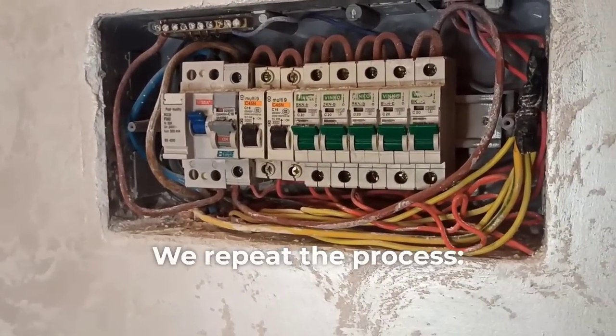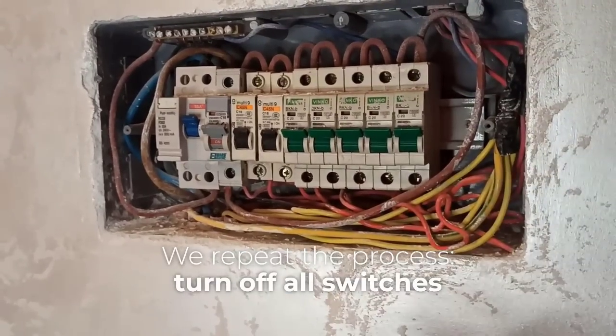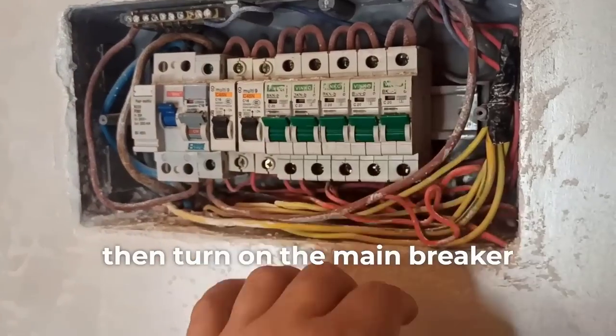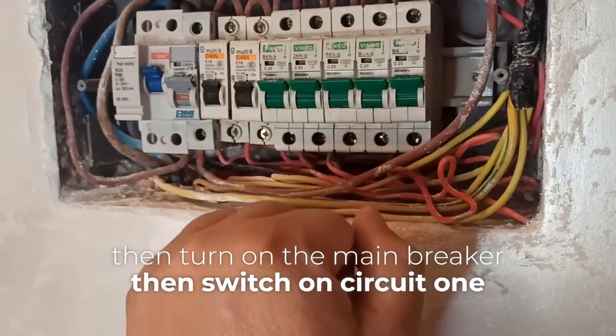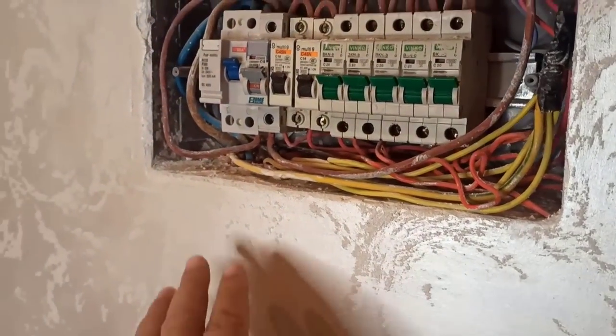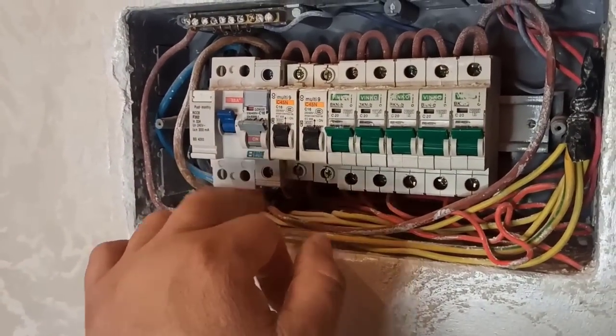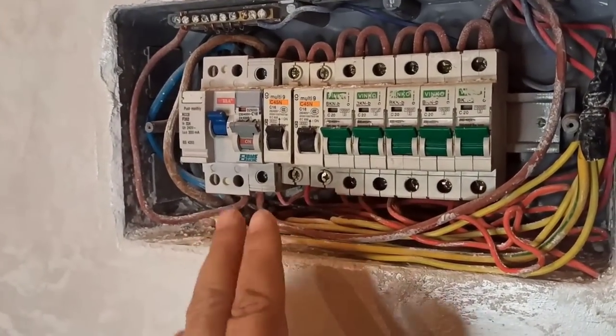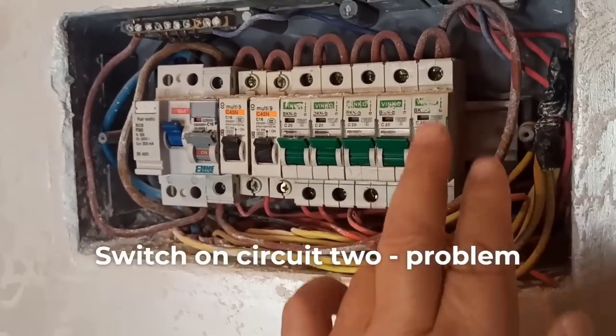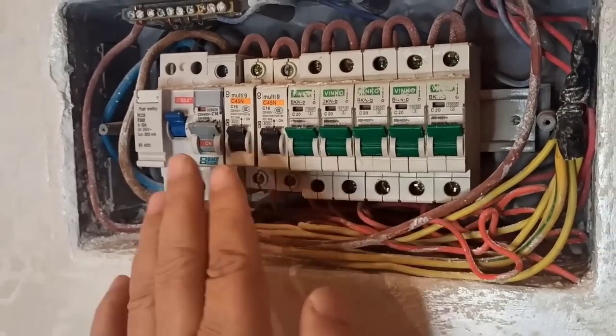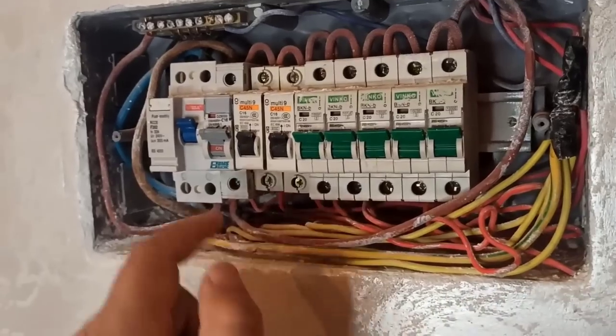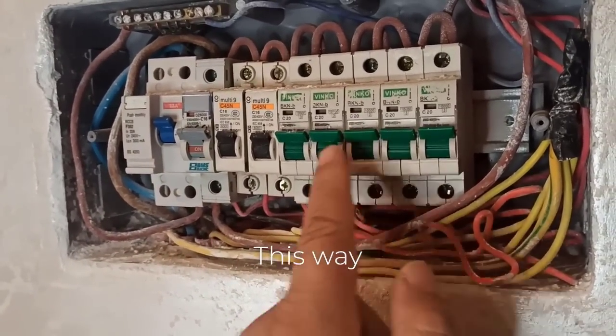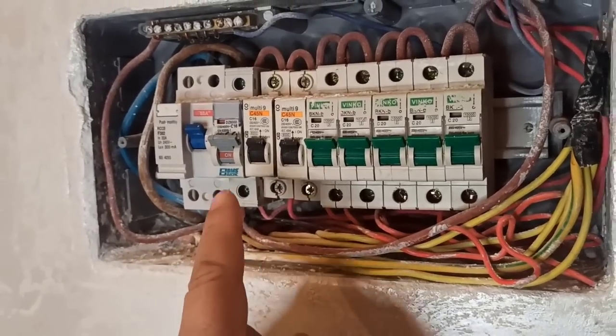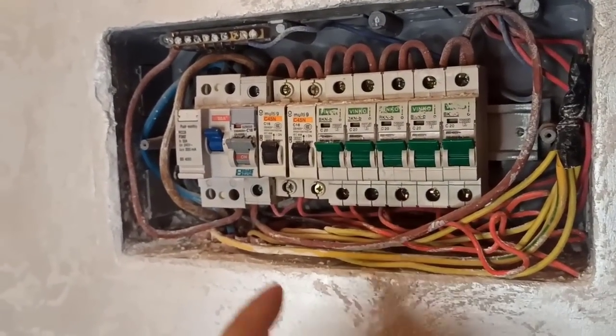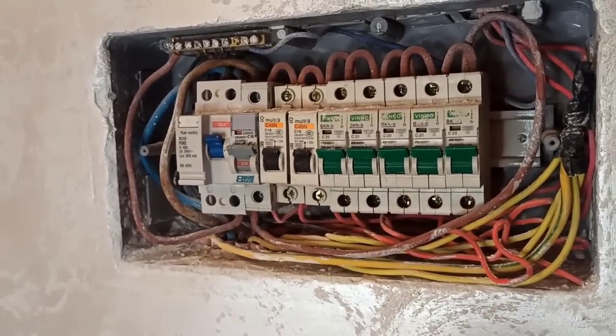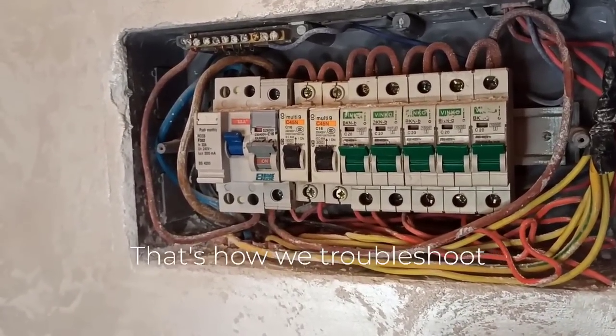We repeat the process. Turn off all switches, then turn on the main breaker, then switch on circuit 1. No problem. Switch on circuit 2, problem occurs. This way, we've identified the faulty device. That's how we troubleshoot electrical issues.